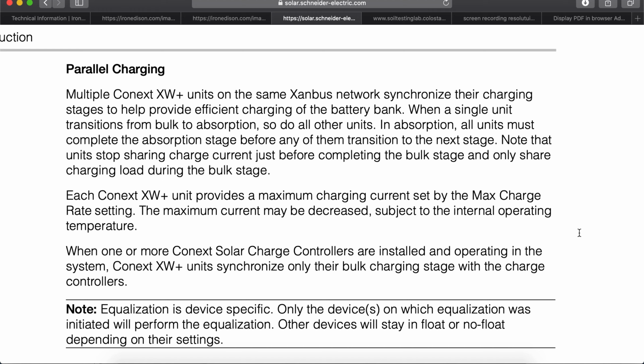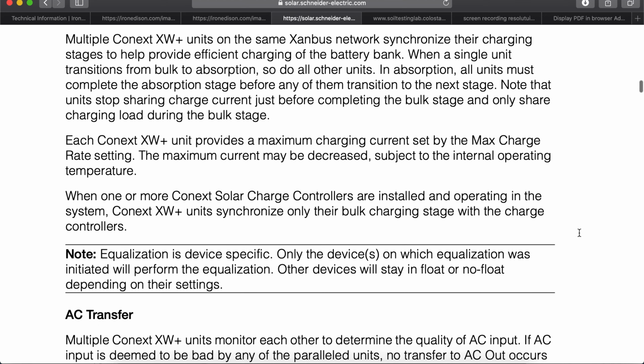Note that units stop sharing charge current just before completing the bulk stage and only share charging load during the bulk stage. Each Conext XW Plus unit provides the maximum charging current set by the max charge rate setting. The maximum current may be decreased, subject to the internal operating temperature. Also subject to our programming.